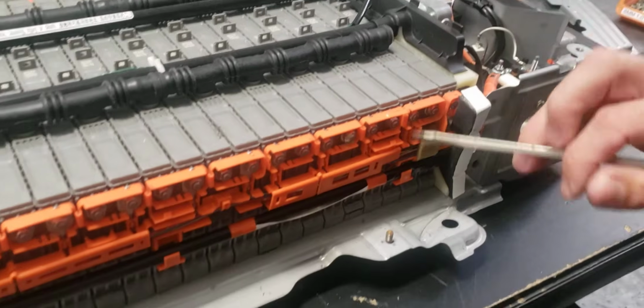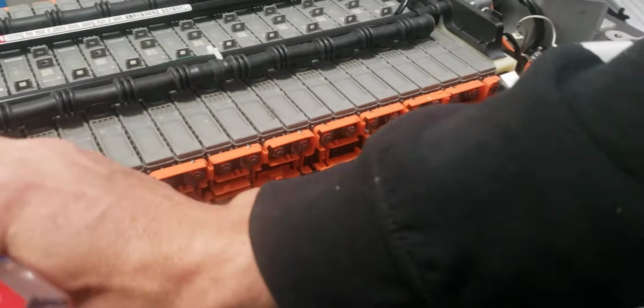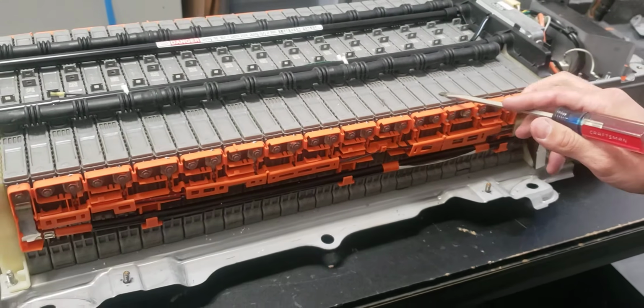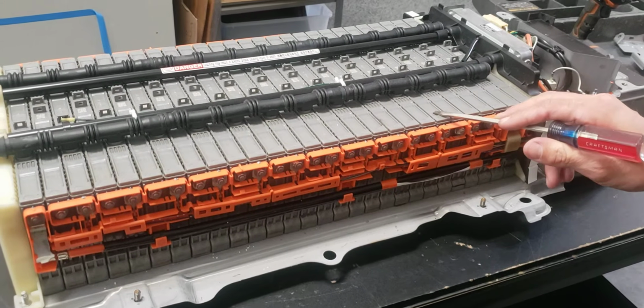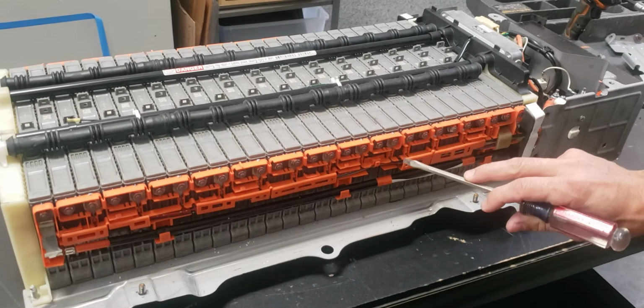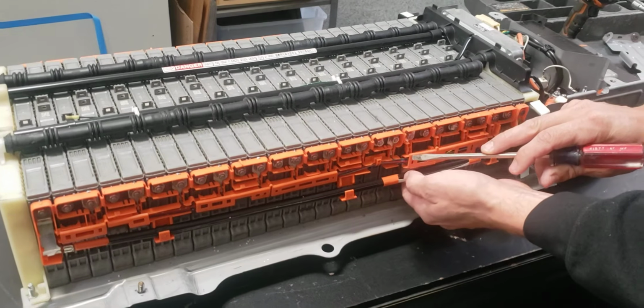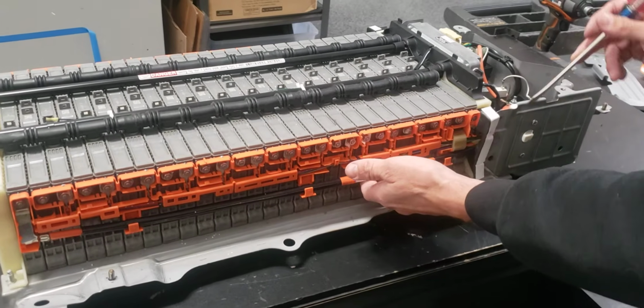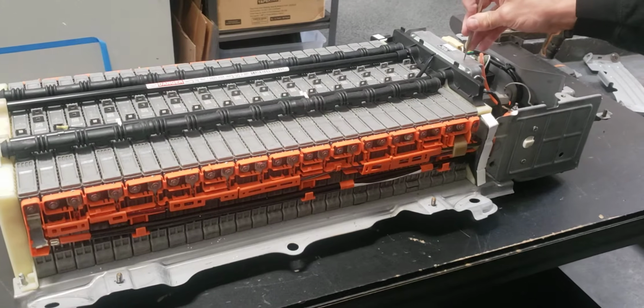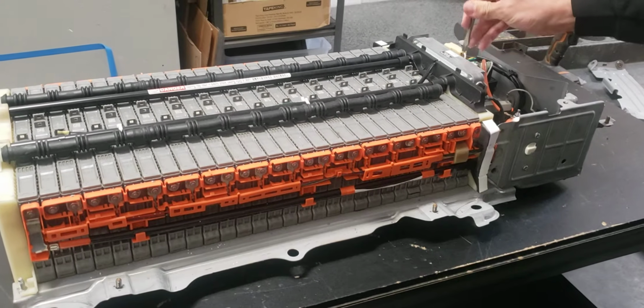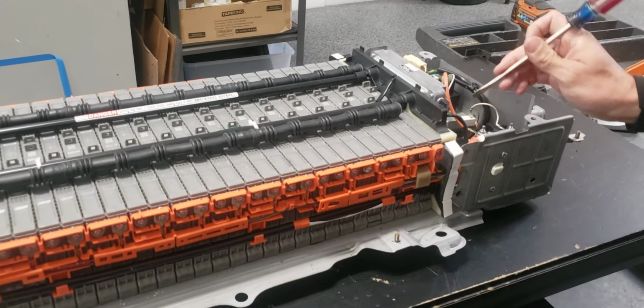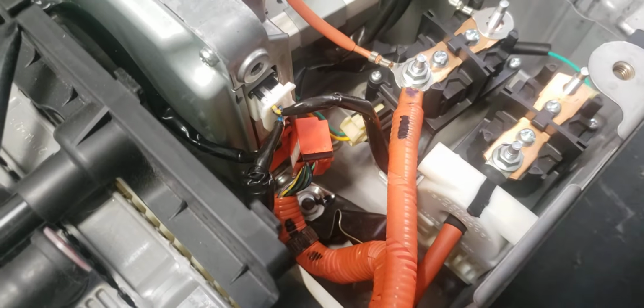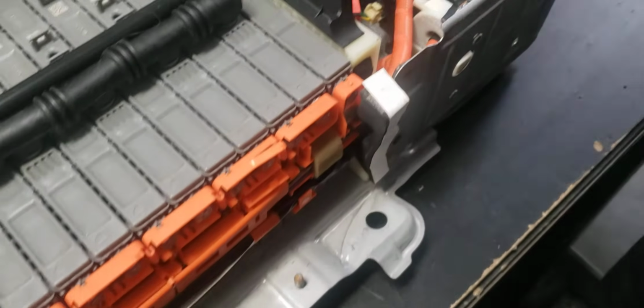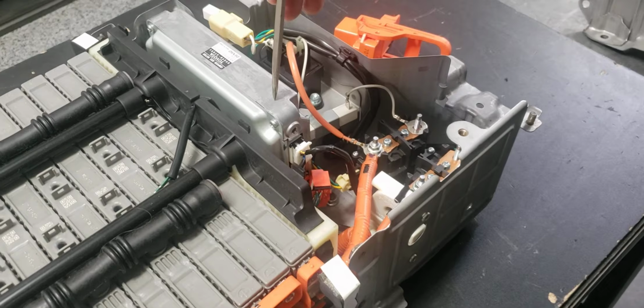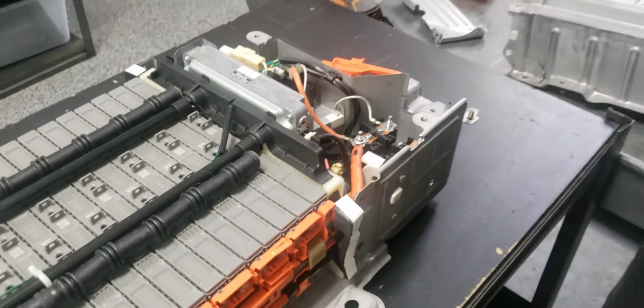When we're doing our insulation test, we're testing the insulation of all of the cells. Anything connected to them is going to be tested for insulation. Each one of these blocks has a single wire that goes to it, and all these wires run in the harness and go into the battery control module, BCM. This is grounded out to here, so you will get a false reading if this is not unplugged. So just make sure you unplug the voltage acquisition wires from the actual module, and that's pretty much it.